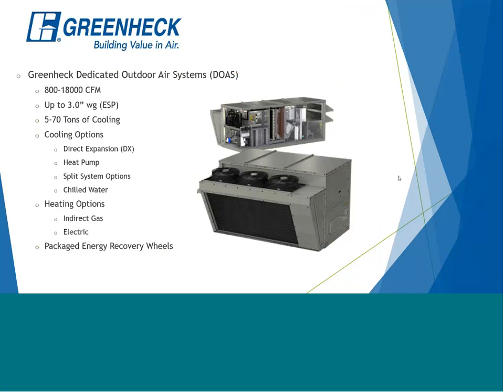Obviously, these come with an optional energy recovery wheel and multiple layers of filtration. We can add 4-inch HEPA filters into these units. Most commonly, these units are designed to be fully modulating in pretty much every way, from variable speed compressors, modulating hot gas reheat, EC condenser fans, variable speed supply fans, and electronic expansion valves. However, there are many different configurations available, but anytime you're introducing large quantities of outdoor air to help promote indoor air quality, that's going to be the best way to go.